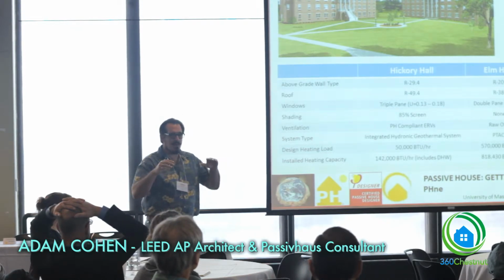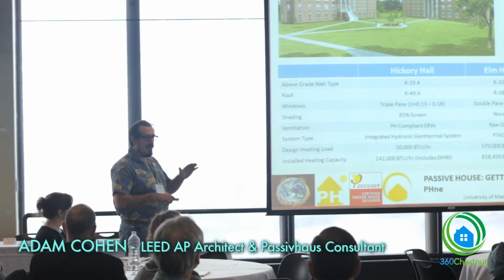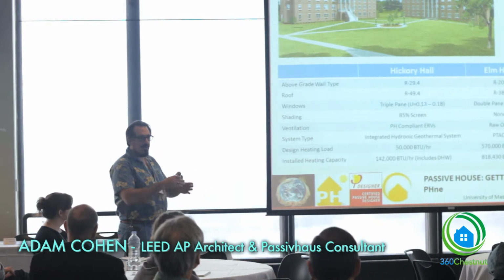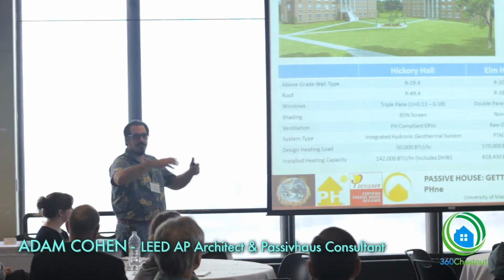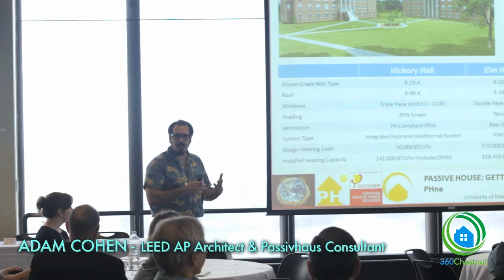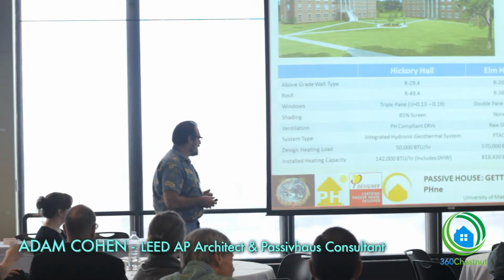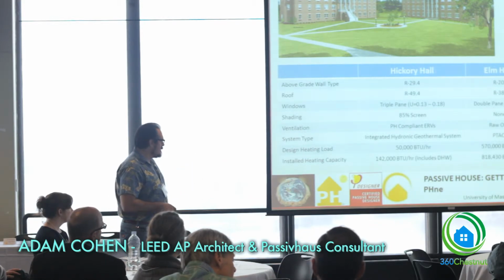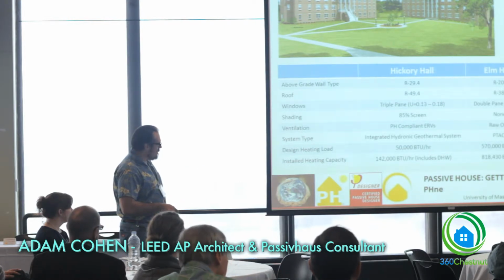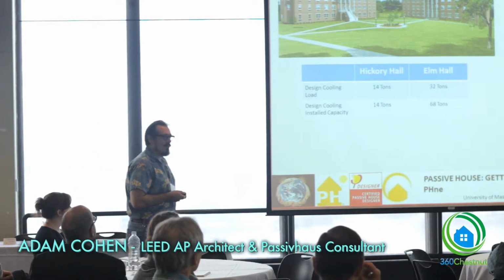In our soils, where we're using ground source, what we've learned over the last 20 years is you've got to balance your heat and cool loading over the year, because if you have an unbalanced situation, it will reduce the efficiency over the course of years, because our soils build heat and hold it. They're semi-insulative. So we were finding we didn't have enough heat to balance the cooling load, so we needed about half to balance it out. And then they have 818,000, that includes their heat. So this is why the economics work so well, right?